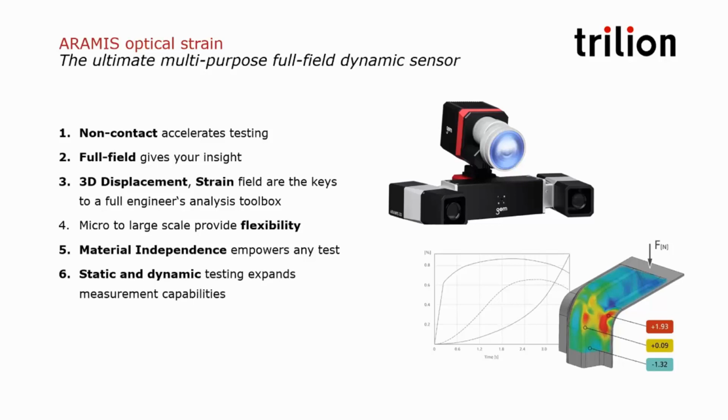And we can move from static to high speed. That means we can do before and after. A good example of this might be an implant placement, for instance, or we could go dynamic with impact testing, inspect hammer strike location or bone saw motion for orthopedics. We also have this integrated massless vibration analysis where you could monitor structural integrity of a bone. And with our FEA validation workflow, you can get your simulations closer to reality than ever before with just a single test iteration.